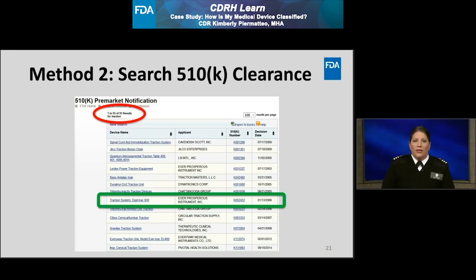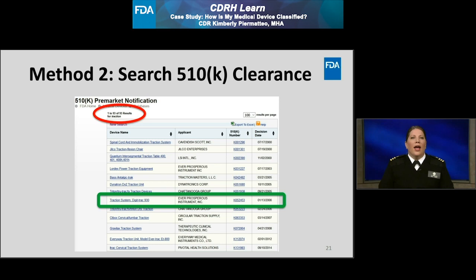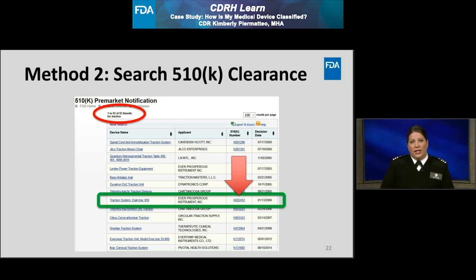The screenshot provided on this slide shows that by searching the keyword traction, I obtained 93 results, circled in red at the top left, and the first 14 results are displayed. Note, I conducted this search in July of 2019. Therefore, if you were to conduct a similar search after this date, you may obtain different results if a more recent device received 510K clearance. For this example, I said I'm looking for the similar device called the Digitrack 930. After reviewing the first few results, I was able to find a device called the Traction System Digitrack 930, highlighted in green. I'm going to select the 510K number, K052453, as identified by the red arrow.